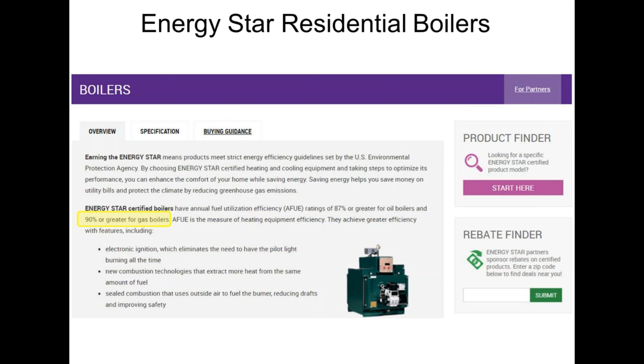That's the efficiency target. There's some other things that it'll probably have. They're not necessarily requirements, but they'll probably have electronic ignition. I probably need that to get the efficiency anyway. I'll probably have heat exchangers that extract more heat, right? And I'll probably have sealed combustion. But I have to get 90%. So basically all condensing boilers are going to meet Energy Star. All non-condensing boilers are not going to meet Energy Star. It really comes down to being that simple.